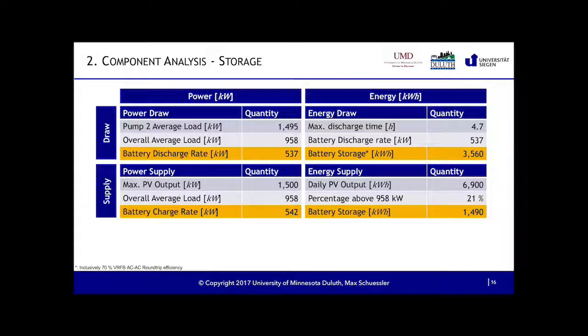And if we look at the supply, what the PV system produces on a really sunny day when the pump cannot run because all the reservoirs are filled up, I would at a maximum need 540 kW to make sure that I can offset all my PV energy and not just let it sit there or shut off the PV system. And the same goes for the energy. I looked at some numbers and came up, for the battery storage when I look at the pumps, with around about 3.5 megawatt hours of storage.